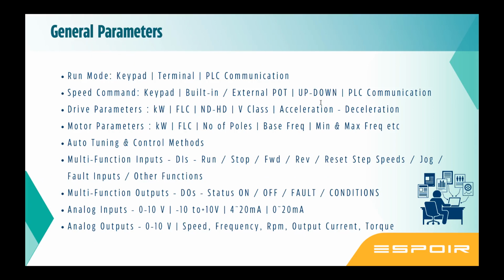Now, once you set the drive parameters, you need to set the motor parameters. Motor parameters like kilowatt, full load current, number of poles, base frequency, minimum and maximum frequency, all that you can set. Then if you do the auto tuning, it will collect more data. And then go for control method selection, control method tuning. Then you have to configure the digital inputs. Here they are called multi-function inputs, which means they are user definable. There are some 60, 70 options given for each terminal. You can define what you want. You want a start stop, you want a jog, you want a reset, you want an external fault, you want a step speed, you want a brake open, brake release.